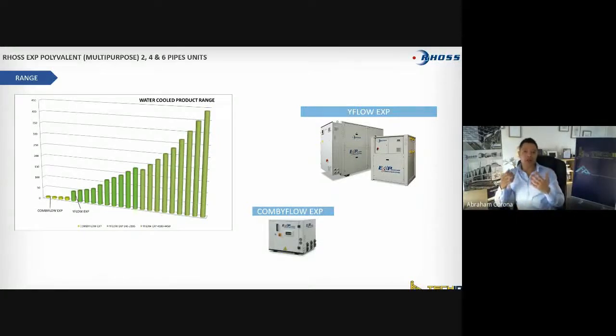One of the main issues when you are designing a 4-pipe unit is the minimum water volume, and it's more important on the heating water side. But both are important. If you underestimate the volume and go with a smaller volume, remember that this unit is automatically swapping between cooling water and simultaneous heating. If the water volume is too small and the temperatures change too quickly, the chiller or the polyvalent unit can start to misbehave, swapping between modes, because they don't know what to do. You don't give them enough time to react.